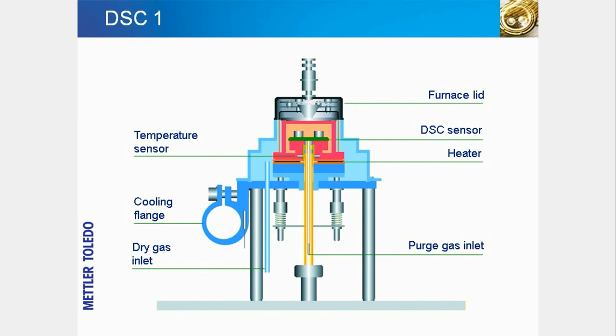This slide shows a schematic view of the furnace in a DSC-1 instrument. The heated parts are colored red, the cooled parts blue, and the DSC sensor green. The temperature sensor inside the silver furnace regulates the temperature via a heater just below the silver furnace. A cooling option is often necessary to perform experiments below room temperature. Cooling is achieved by means of a flow of air around the furnace, or by using a cryostat or an intracooler.